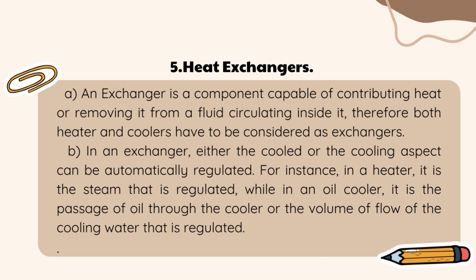5. Heat exchangers. A. An exchanger is a component capable of contributing heat or removing it from a fluid circulating inside it. Therefore both heaters and coolers have to be considered as exchangers. B. In an exchanger, either the cooled or the cooling aspect can be automatically regulated. For instance, in a heater, it is the steam that is regulated, while in an oil cooler, it is the passage of oil through the cooler or the volume of flow of the cooling water that is regulated.